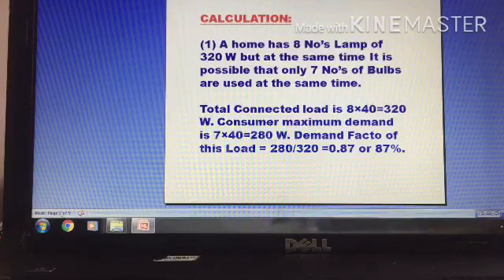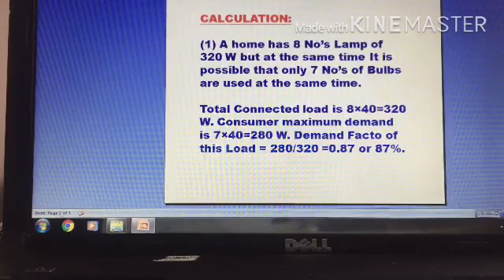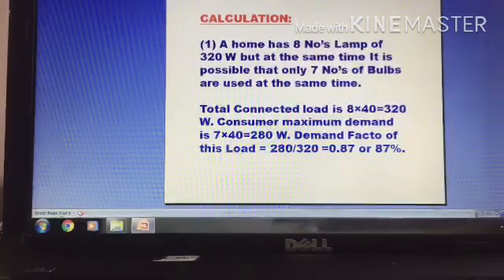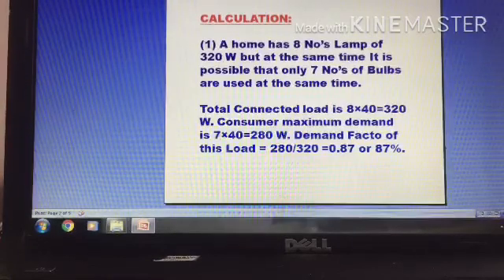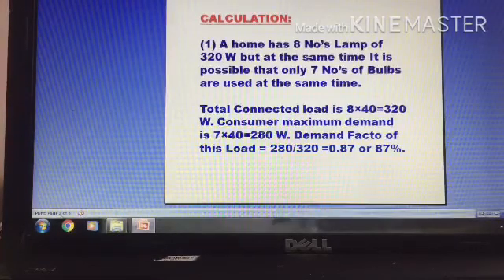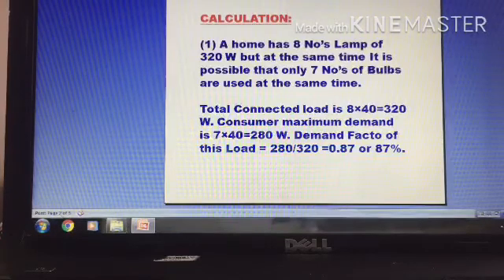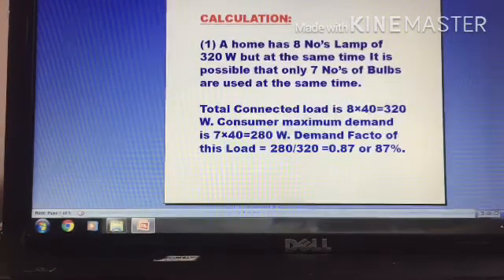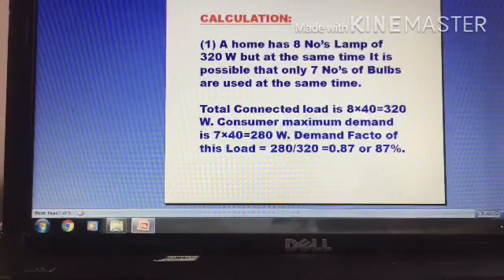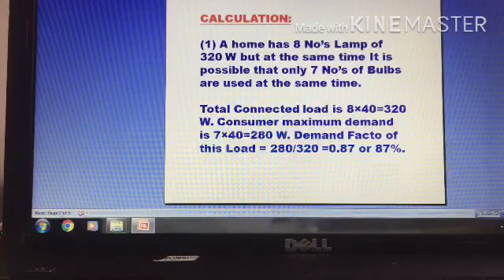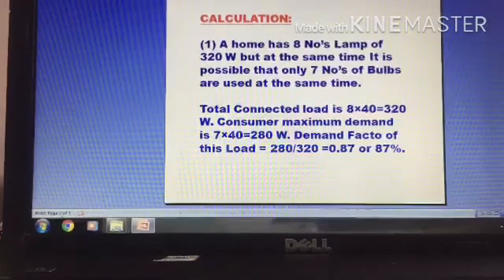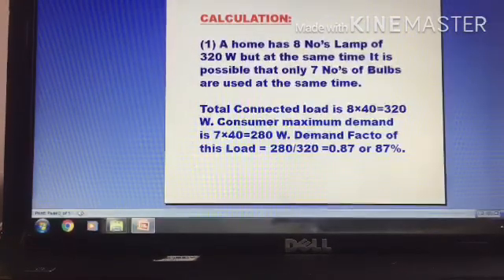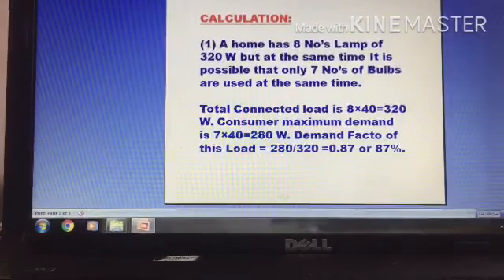Let's look at another example. There is a lamp and tube lights. Each tube light is 40 watts, and there are 7 tube lights in use out of a total connected load of 320 watts. So 7 times 40 equals 280 watts used. The demand factor is 280 divided by 320, which equals 0.87.